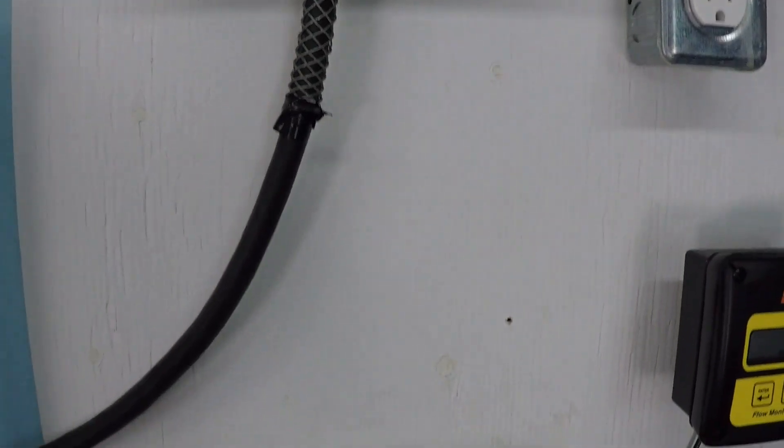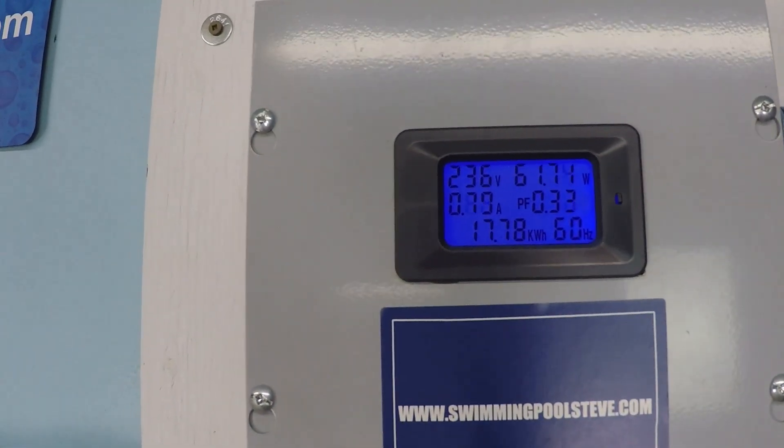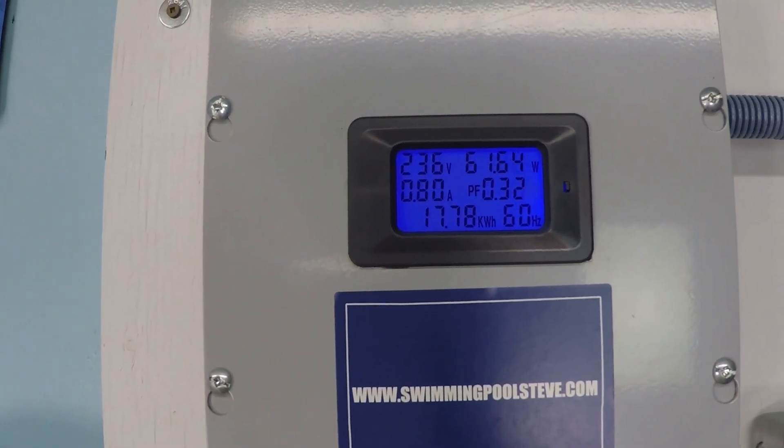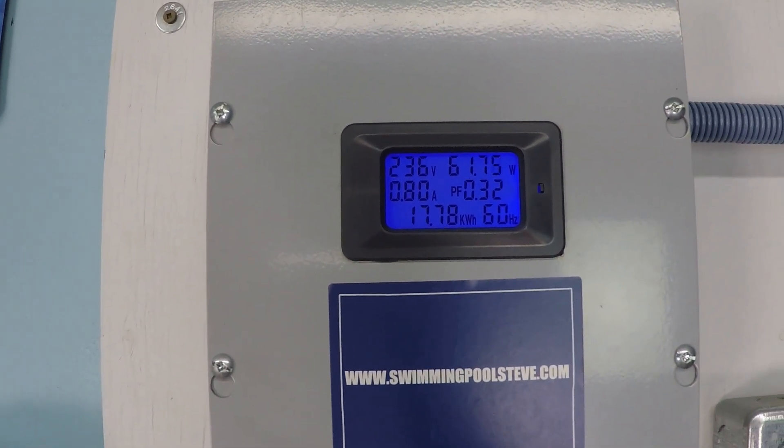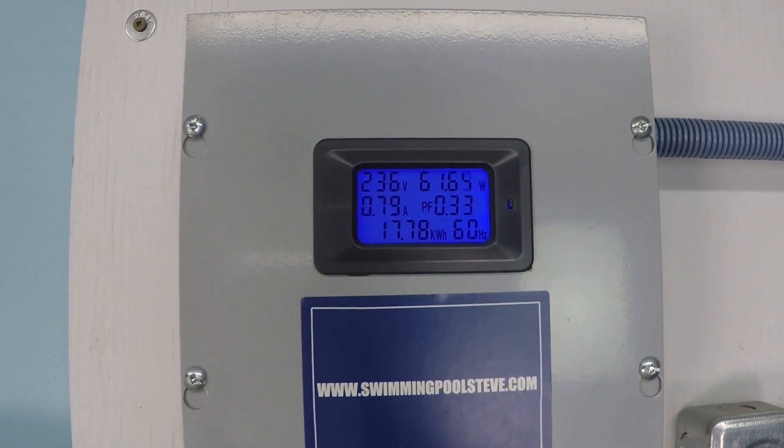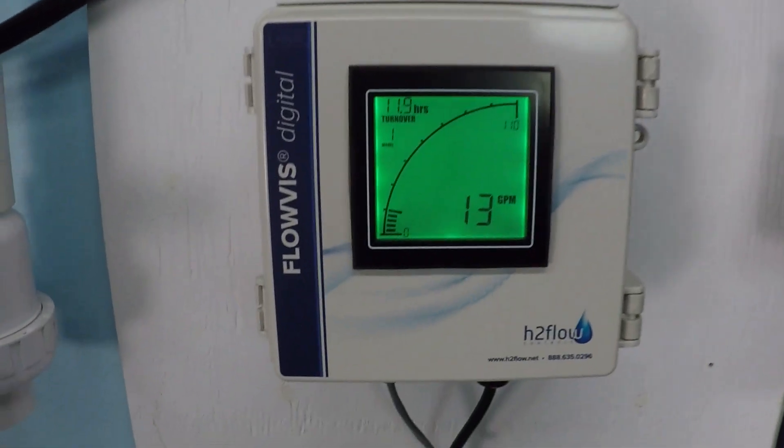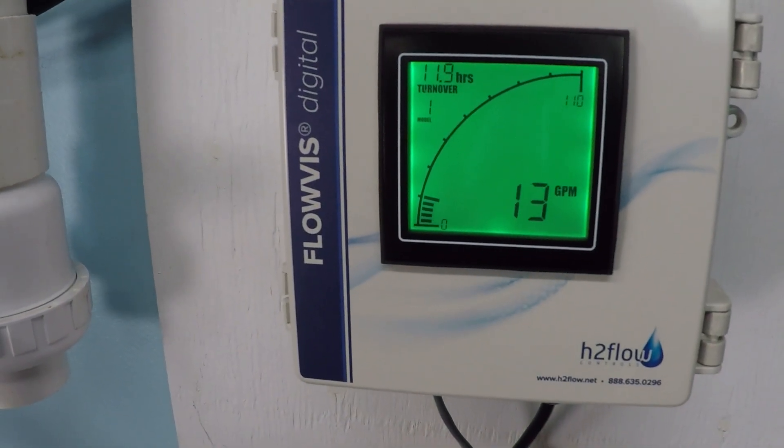Let's take a look at the power consumption. 61 and a half watts is how much power the pump is consuming in order to achieve 13 to 14 gallons per minute.